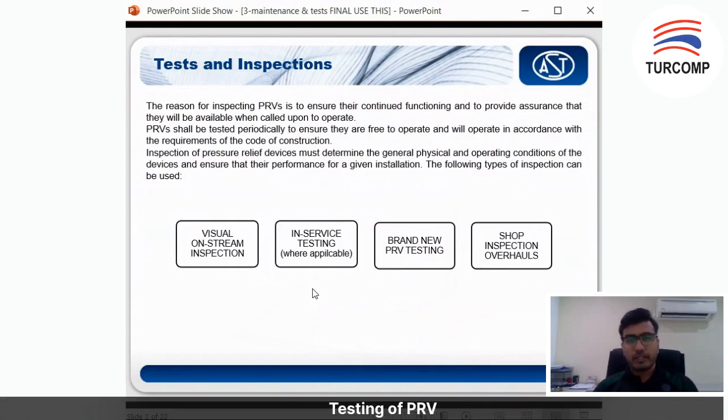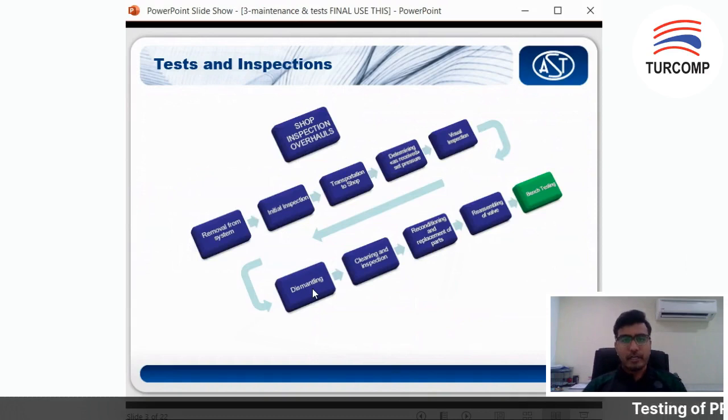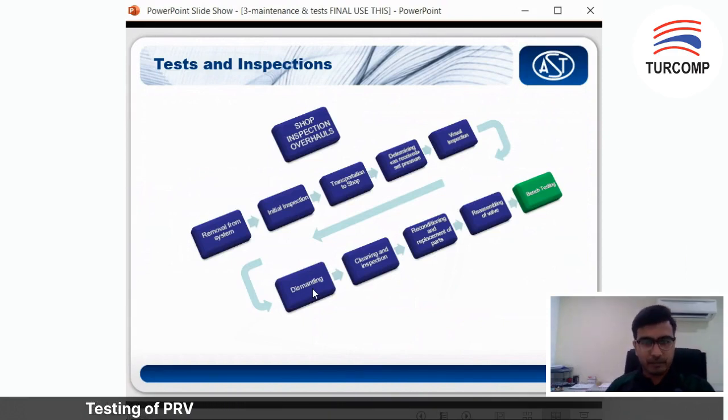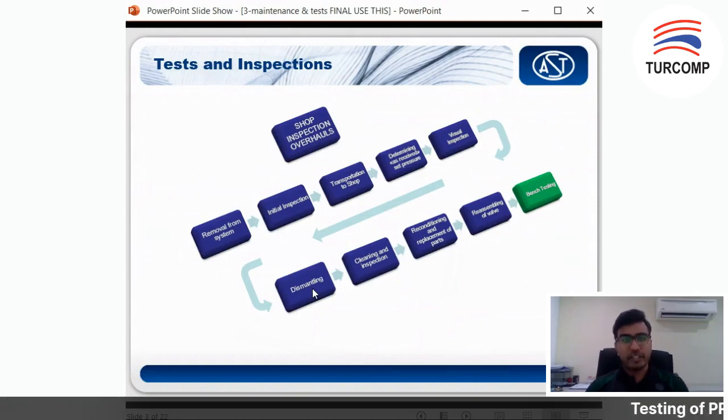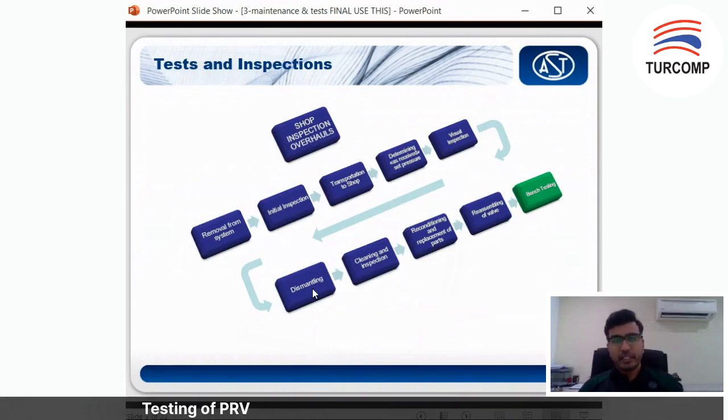Next, you test it at the test bench for brand new PSVs and also for shop inspection before overhaul. Usually, they will retest the valve, and once you change any spare parts on it, you will test again. This is the typical flow on how you service your PRV. First you need to remove it from your system, then you need to have an initial visual inspection — whether it is corroded, whether there is any deterioration of the valve — and transport it to an inspection shop.